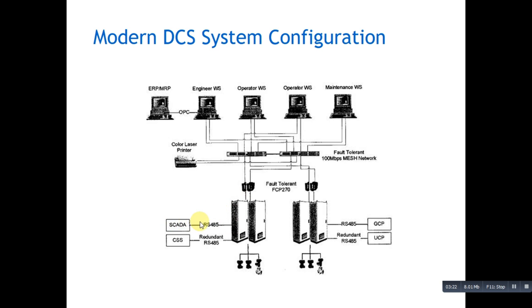It communicates with the SIS, or Safety Instrumented System, on RS-485 independent plane, with the UCP, the Unit Control Panel for the gas turbine, and with the GCP, the Generator Control Panel, on RS-485. From this, it goes to the fault-tolerant FCP-270 redundant controllers.